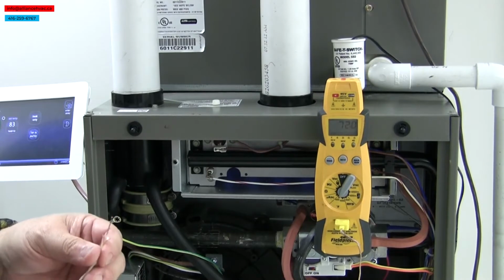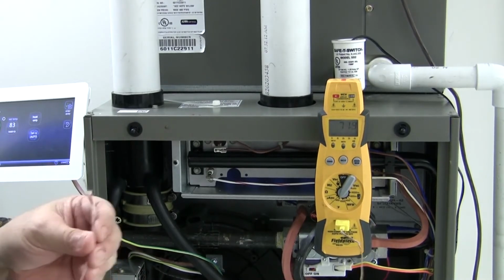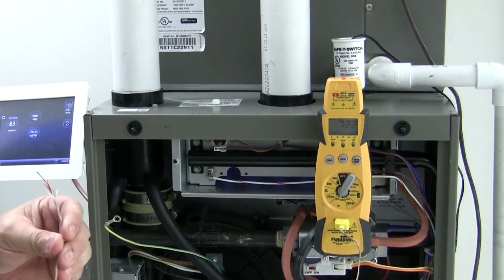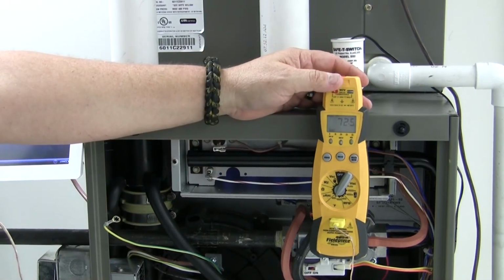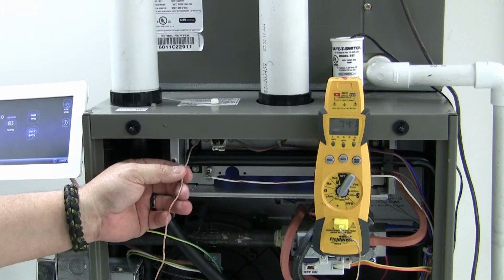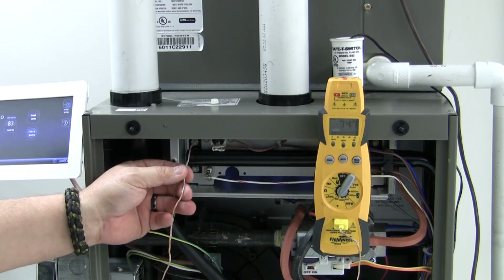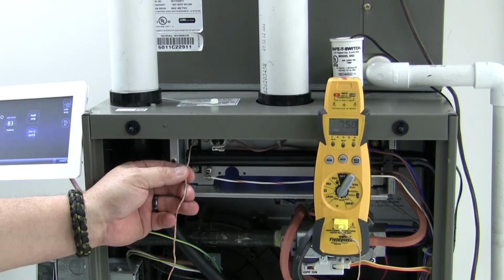To actually measure or test and make sure your rollout switch is okay, you're going to need a temperature thermometer. We're simply going to hold the thermometer probe near the rollout switch so that it's seeing the same temperature as your probe, and that temperature should be somewhere close to room temperature.